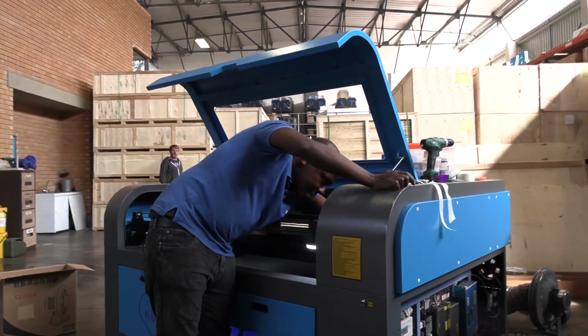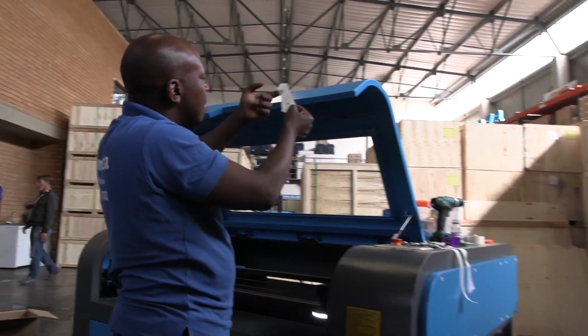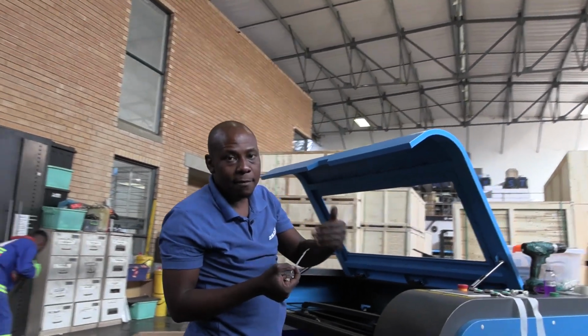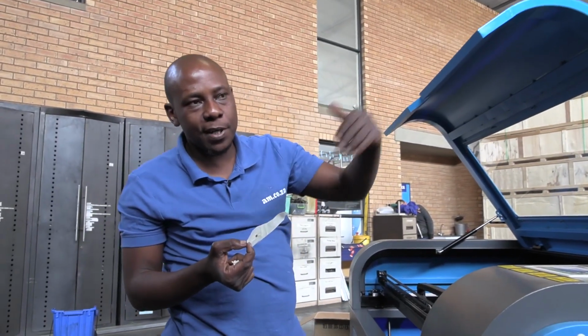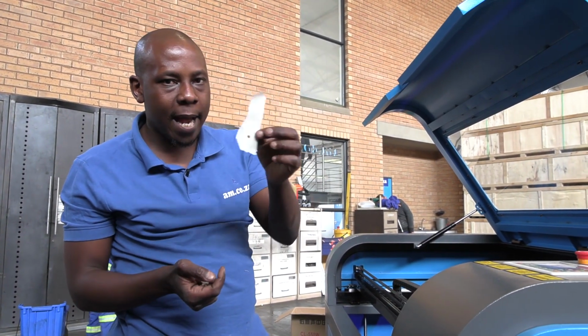Looks like it's aligned. So what I'm going to do is peel out both of the tapes. Look through the light and I can actually see they are burning on the same position, meaning my y-axis is now aligned closest and furthest away from the first mirror. Same applies. I need to clean that mirror which I had this tape on. Once you are happy with aligning your y-axis, you can move over to aligning your x-axis.